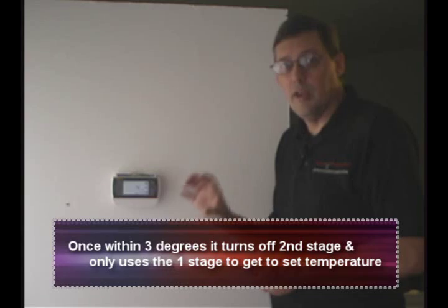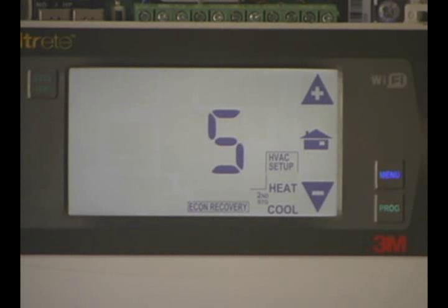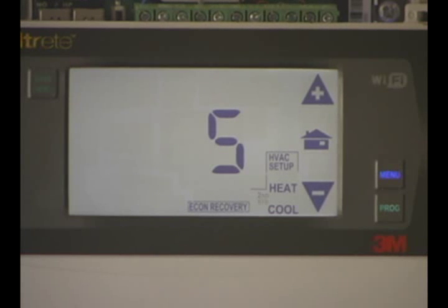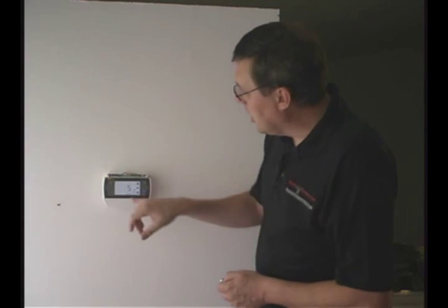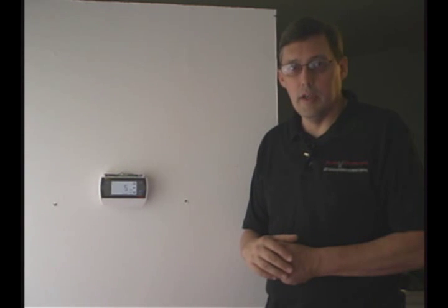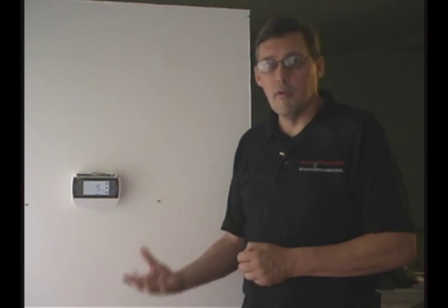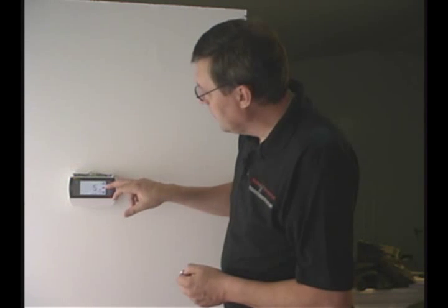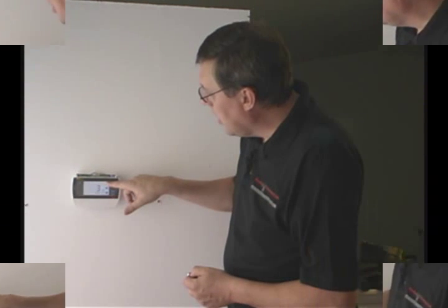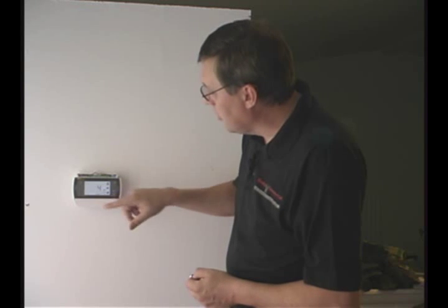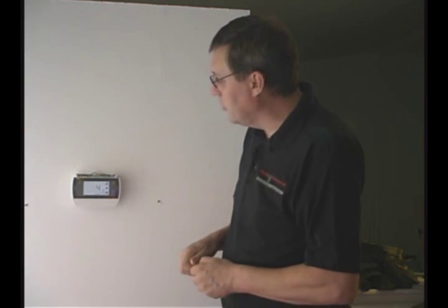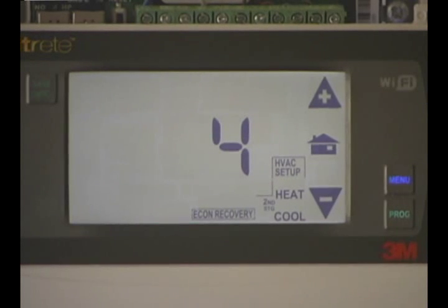This is more economical but takes a longer period of time to reach that temperature. Number 5 shows economy recovery with the 2 flashing, meaning 2 stages of cool and 2 stages of heat. The cool works the same way — when you get to the differential in economy mode, it goes back to the 1st stage, which saves energy. I like economy recovery because it saves me money, and I only have 1 stage of cool and 2 stages of heat, so I am a number 4.